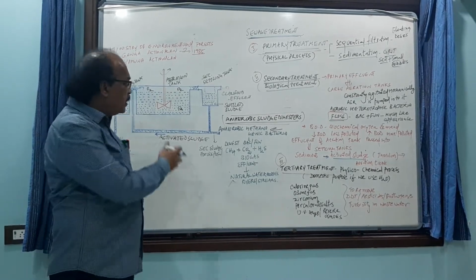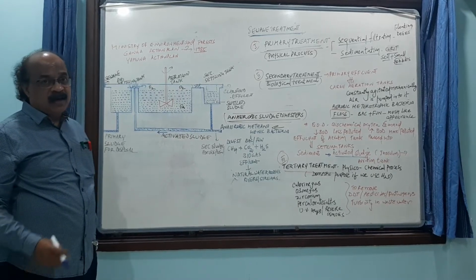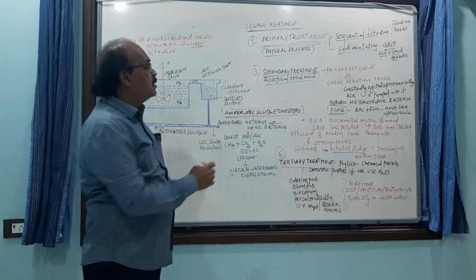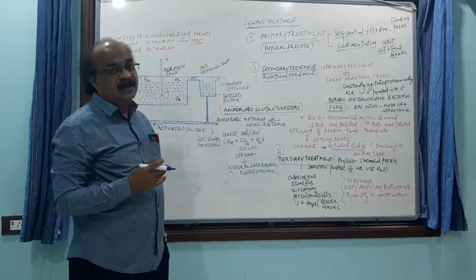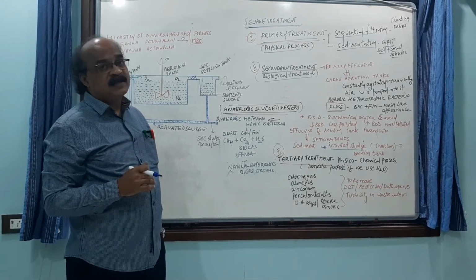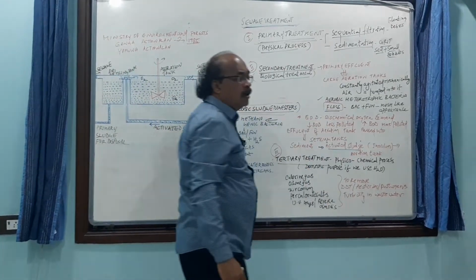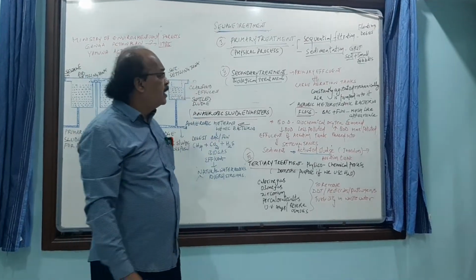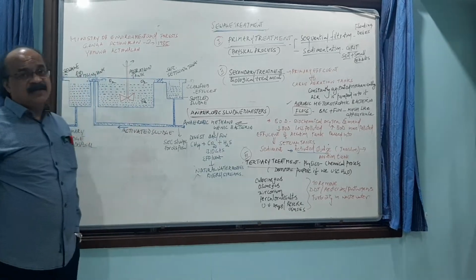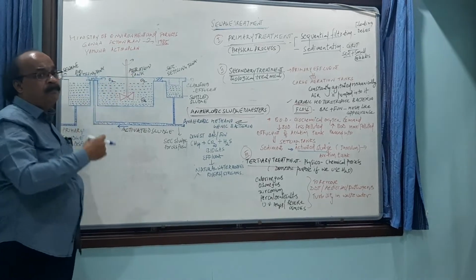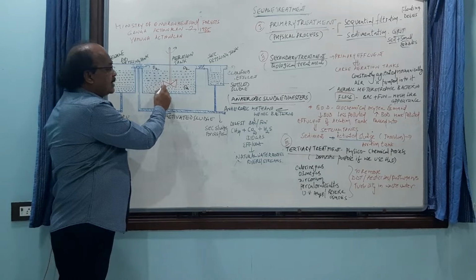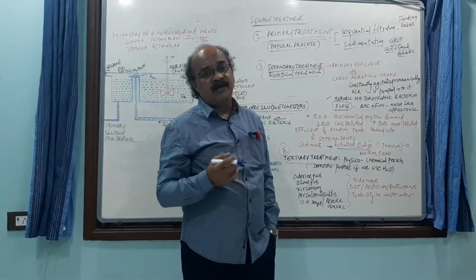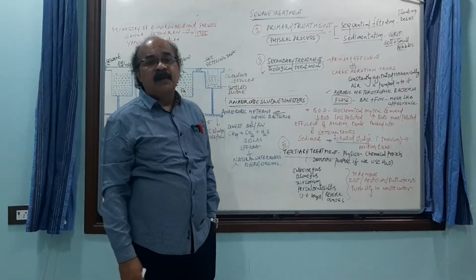Biological treatment. In this particular sewage, organic stuff will be there, because we just dump even the waste food materials into the drainages. So in this secondary treatment, which is said to be biological treatment, the organic materials are oxidized by using aerobic heterotrophic bacteria, aerobic heterotrophic microbes, and also of course the fungi. While the process is taking place in the aeration tank, continuously the air is pumped into it and mechanically it is agitated. As the aerobic bacteria and the fungi are involved, it is said to be a biological treatment.